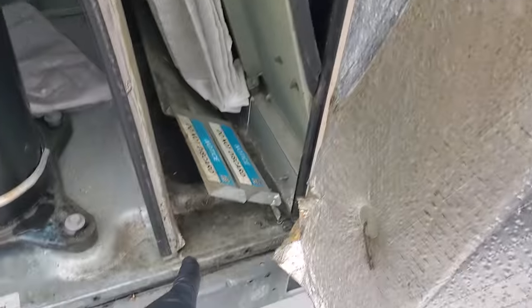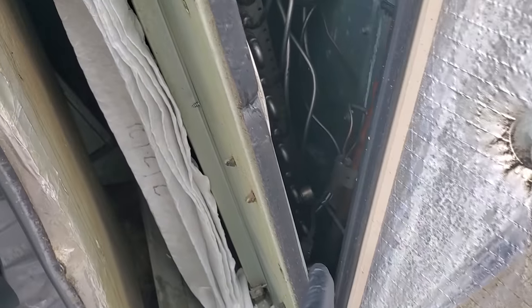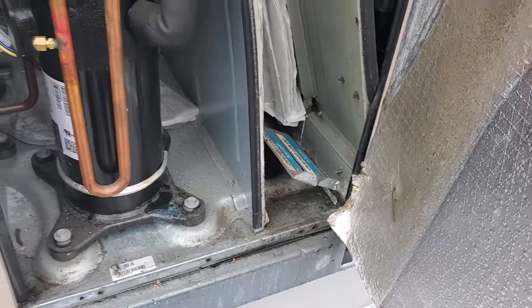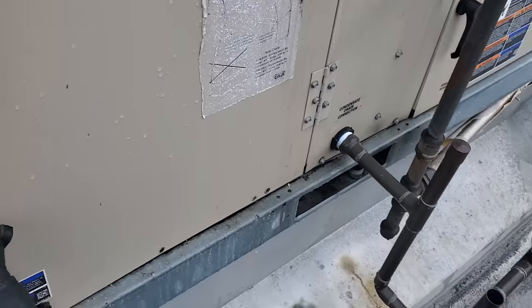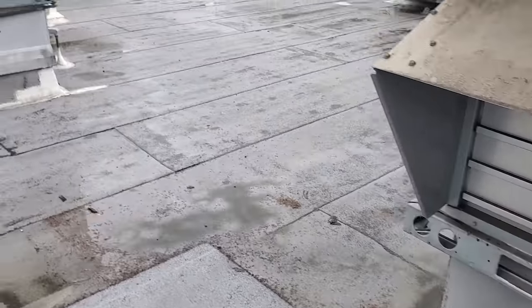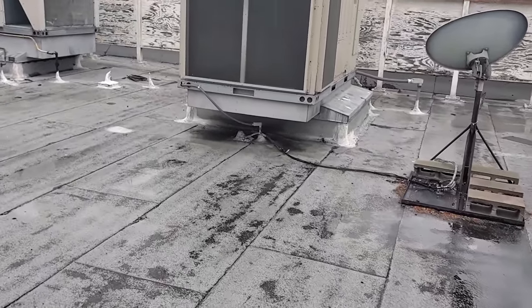You can see there's water in here, but I don't see it in the drain. We'll have to go through this unit and see why there's water in it. I'm sure it's just going to be plugged-up drains and stuff. We're going to check every AC because I believe they said it was leaking in the server line too.